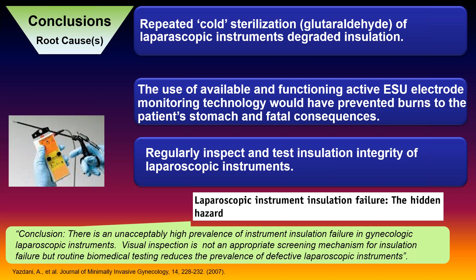So the bottom line is that the sterilization caused the issue. What's being recommended, though I can't imagine too many sterile services departments doing this, is that there are testers out there to check the insulation on these laparoscopic instruments, because with a visual inspection you can't tell if that insulation is intact or not.